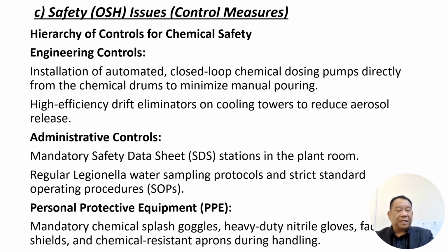So the control measures here: through engineering controls, we install an automated closed-loop chemical dosing pump directly from the chemical drums to minimize manual pouring. High-efficiency drift eliminators are implemented on the cooling tower to reduce aerosol release. Another way of control is administrative control, whereby we place a mandatory SDS station at the plant room, and a regular water sampling protocol, with strict standard operating procedures. PPE is mandatory during the handling of the chemicals: chemical splash goggles, heavy-duty nitrile gloves, face shield and chemical-resistant apron.